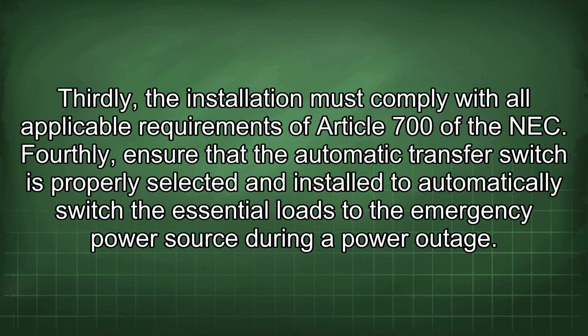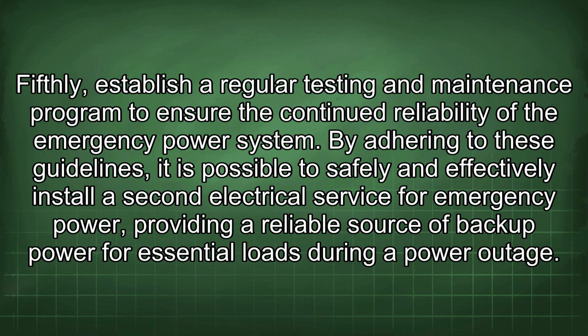Thirdly, the installation must comply with all applicable requirements of Article 700 of the NEC. Fourthly, ensure that the automatic transfer switch is properly selected and installed to automatically switch the essential loads to the emergency power source during a power outage. Fifthly, establish a regular testing and maintenance program to ensure the continued reliability of the emergency power system. By adhering to these guidelines, it is possible to safely and effectively install a second electrical service for emergency power, providing a reliable source of backup power for essential loads during a power outage.